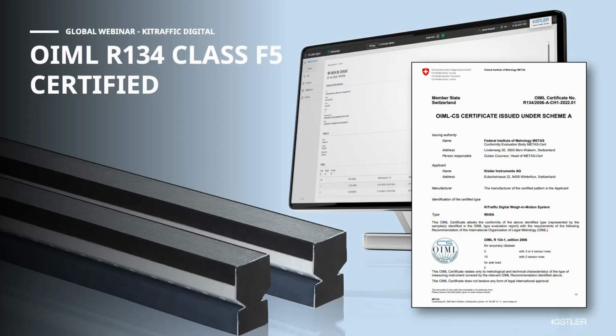But Christoph, what does this certificate state about the maximum permissible error? Well, first we need to understand the concept of this maximum permissible error. It states that 100% of the measurements must be within the specified limits. No outliers are allowed, and no statistical evaluation indicating a confidence level is allowed.